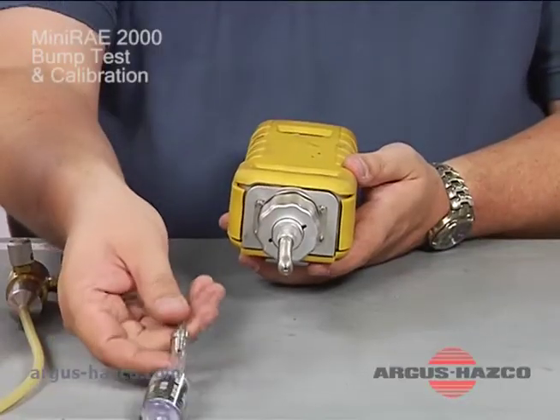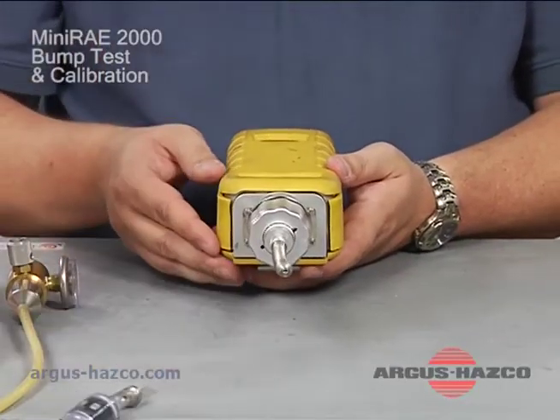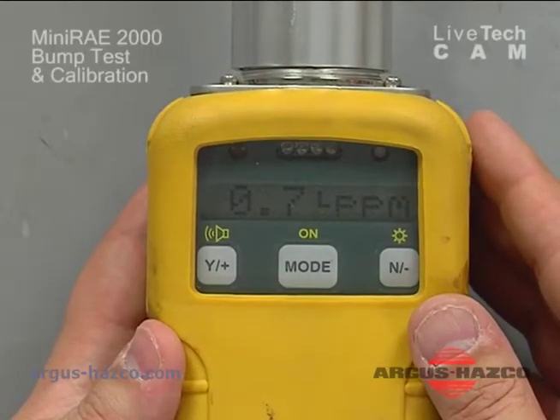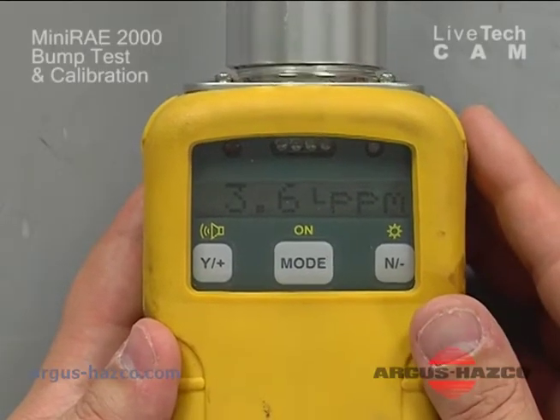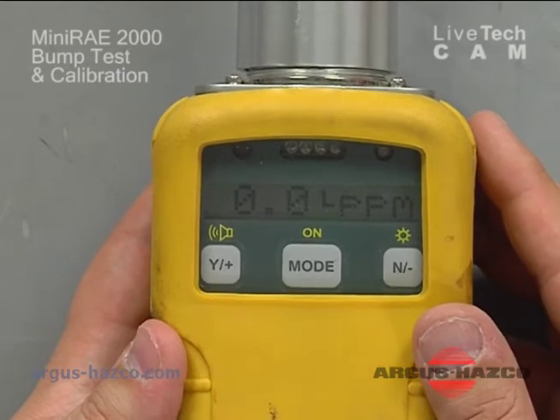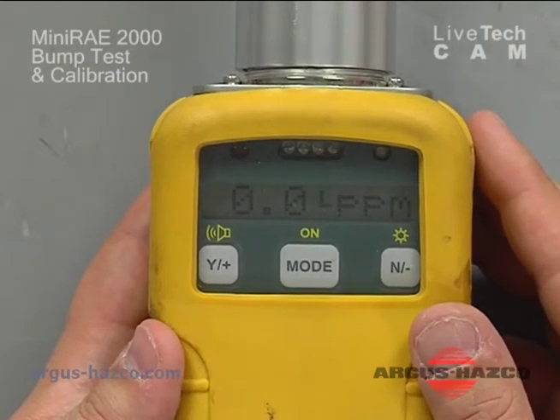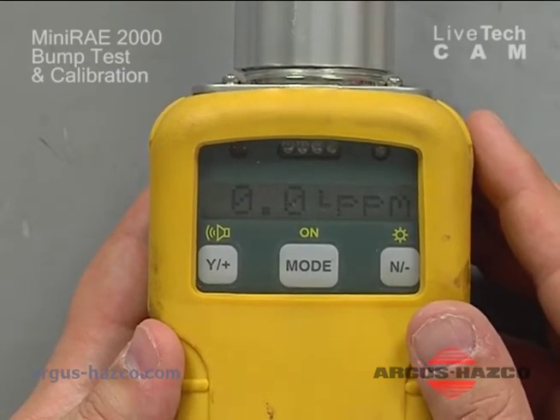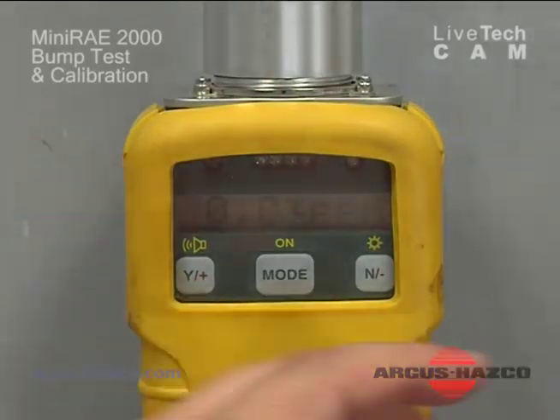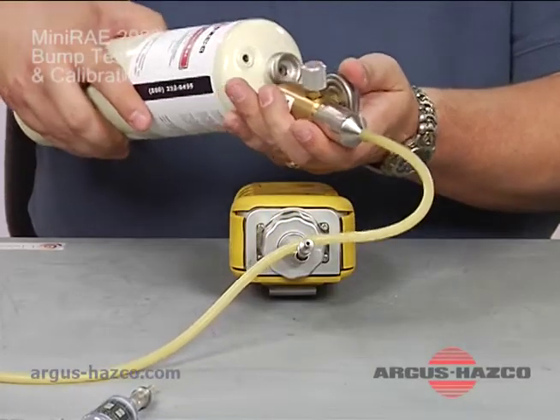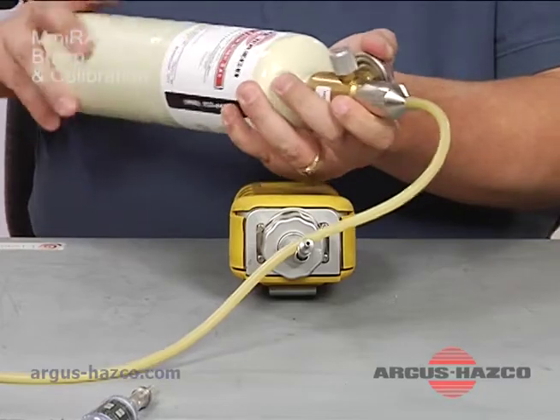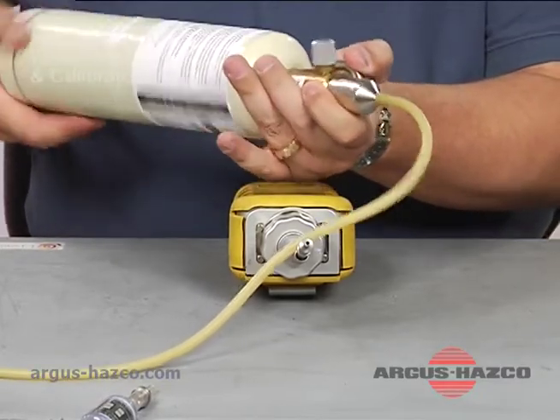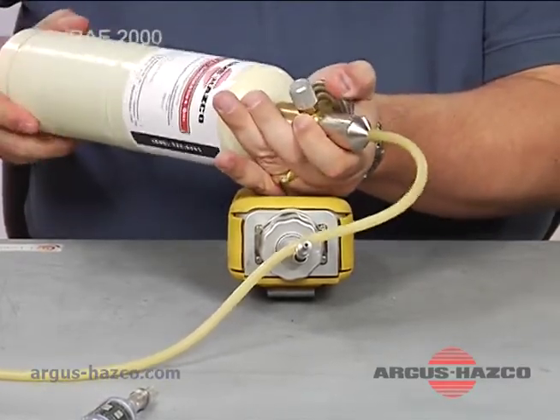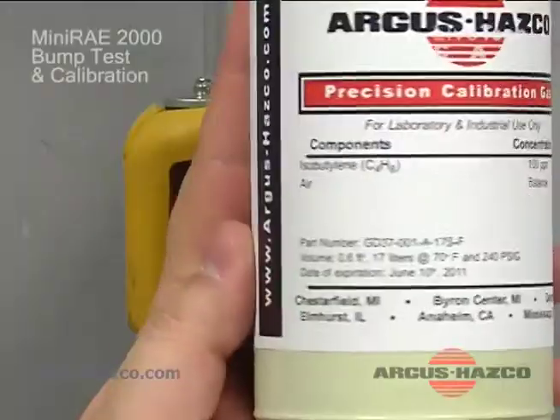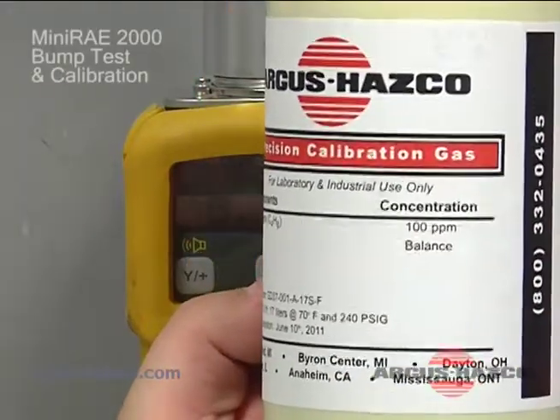At this point, you can see the reading bouncing around. Give it a few seconds to clear. If you do see some drift, that could indicate that the lamp needs to be cleaned and or the sensor cleaned. But at this time, what we're going to do is connect the cylinder to the regulator by screwing it in. Again, isobutylene, 100 ppm.